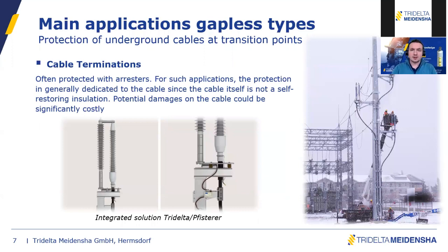Another application, which is not always mandatory like the transformers, but quite common, is the cable termination, where you often see surge arresters. So this is the transition point between the overhead conductors and the underground cables. For such an application, the protection is dedicated to the cable itself, because, as you know, underground cables do not have a self-restoring insulation.